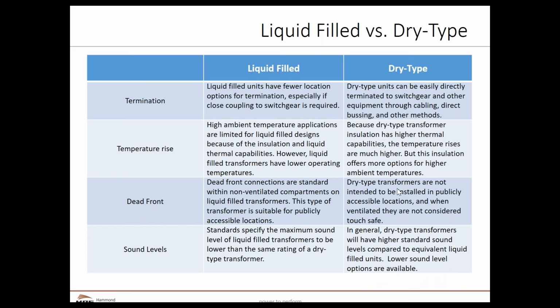Terminations. Liquid-filled have fewer options for terminations. Again, generally you have a front-mounted wiring compartment, and all terminations have to be within certain locations in that small wiring compartment. With a dry type transformer, you have much larger ability to bring in cabling from below, from the roof, from the sides than you do with the liquid filled. So again, a lot more flexible in the cabling and busing methods for a dry type.